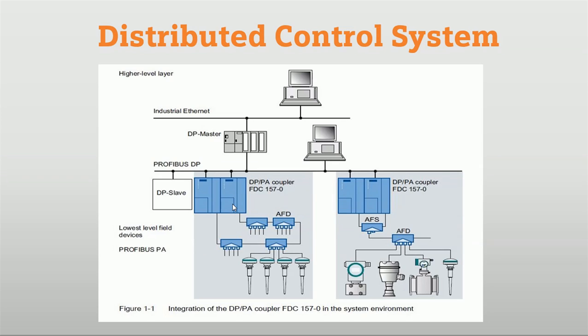Here we use AFD or AFS. AFS is the active field splitter, used for making redundancy with the coupler. We connect two DP/PA couplers so when one coupler fails, the second coupler takes over for communication. With the help of AFS, field devices can connect with the main automation station. The active field distributor (AFD) is used for connecting field devices with the coupler. Using ring redundancy, when any active field distributor fails, the coupler can carry data to the automation station. This is how AFD and AFS are used to establish redundancy in the DCS system.